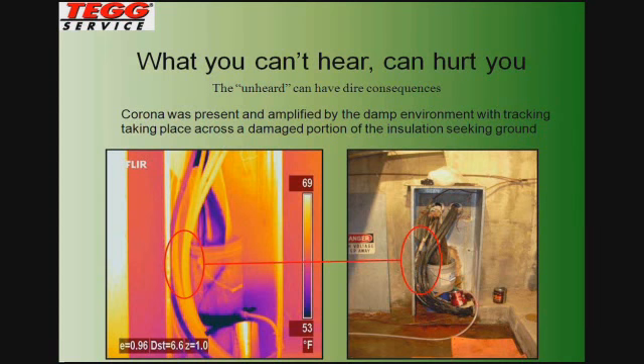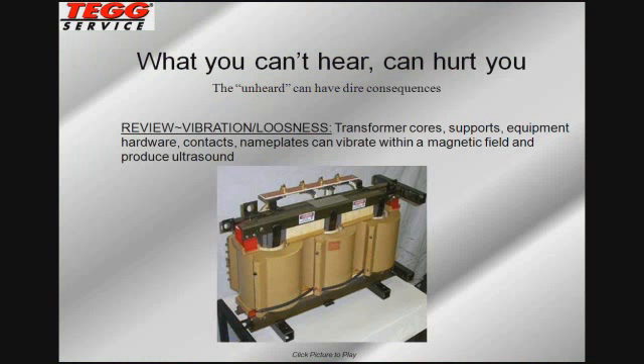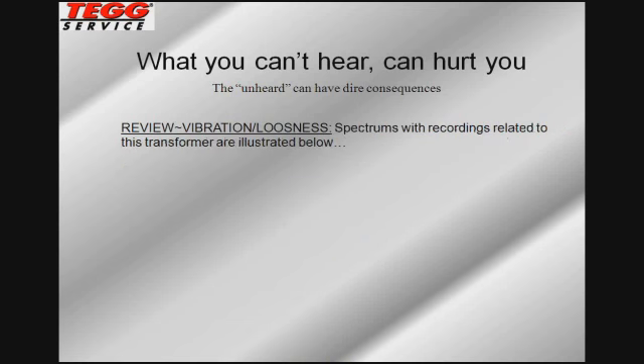The consideration with electrical is vibration and looseness. Depending on what we're looking at, in particular with transformers, we have a lot of cores, supports, hardware, wedges, nameplates, and things like that that react very interestingly with magnetic fields. That's what we have in transformers, a concentrated magnetic field, and that will produce ultrasound. It doesn't always mean it's a problem.